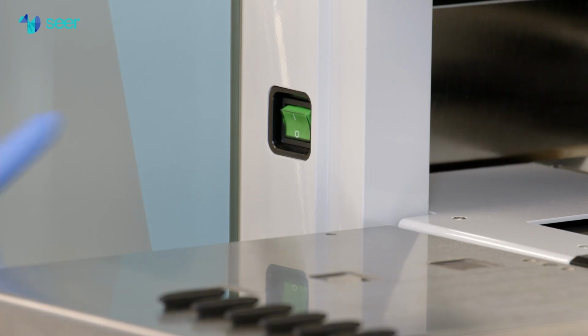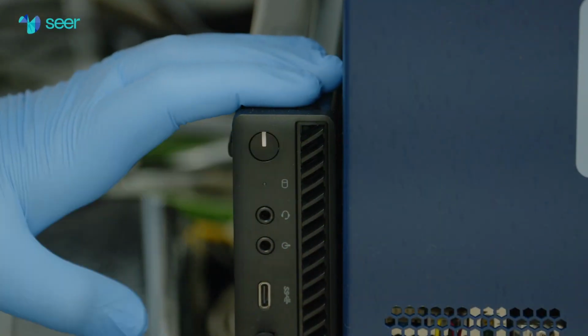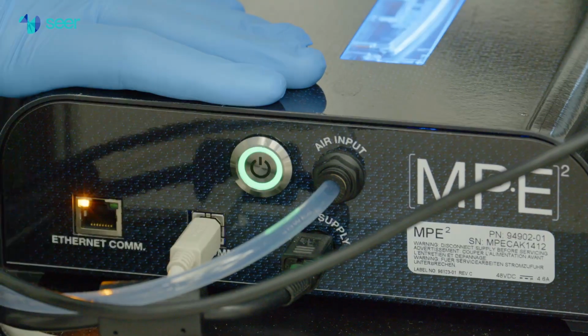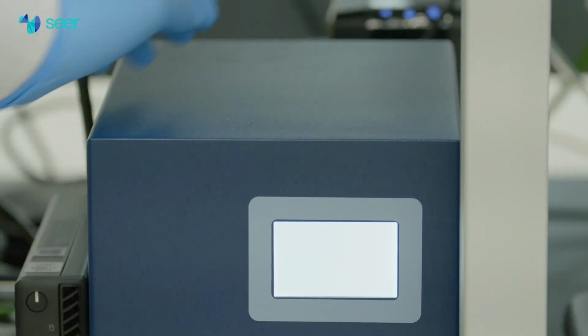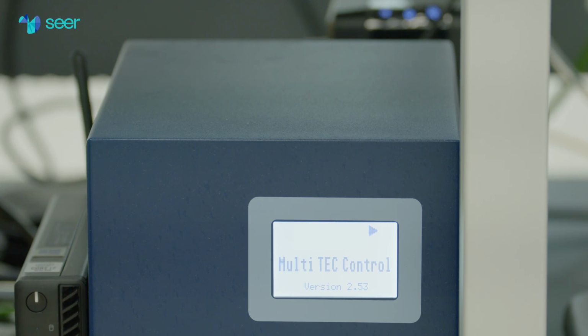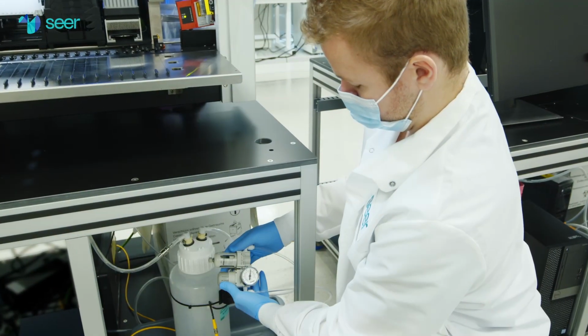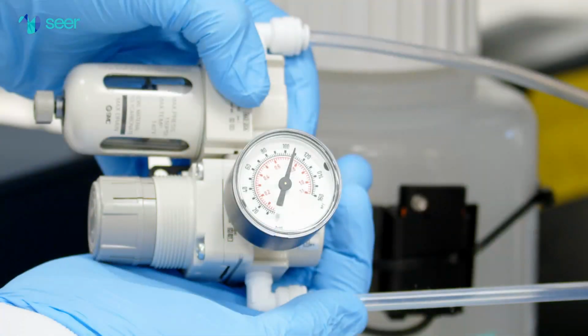We're ready to power on the SP100 automation instrument. First, we will power on the SP100, the instrument computer, the MPE power unit, and the chiller unit. Check the gas supply for the appropriate pressure. Confirm that the MPE regulator is set between 105 and 110 psi.